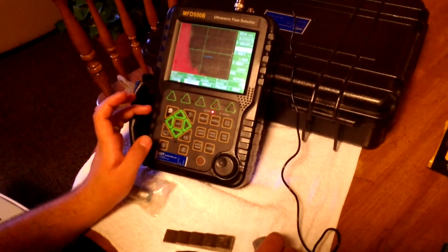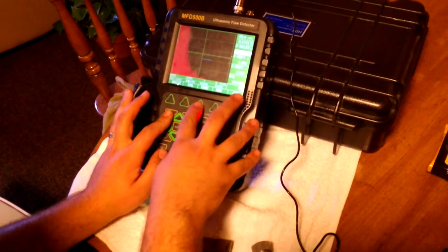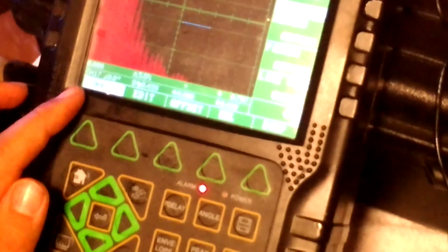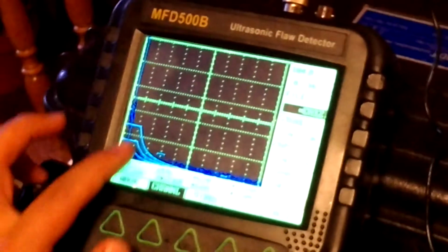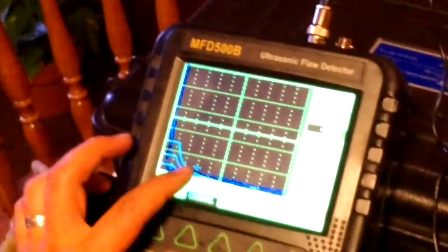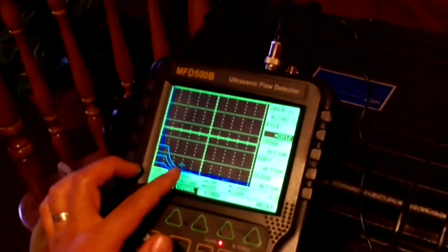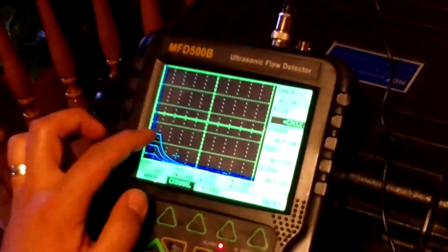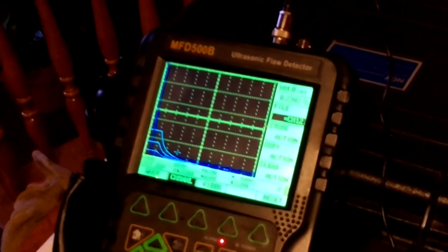Now there is another kind of calibration, which is the calibration from distance amplitude correction, and that curve, the distance amplitude correction curve, is something like this. These curves show that if you have two anomalies with the same size but at different locations, they should show up on the same curve. And that's another type of calibration called distance amplitude curve.